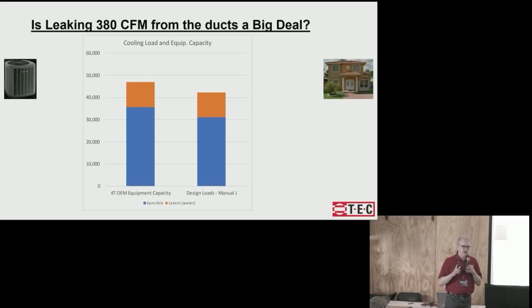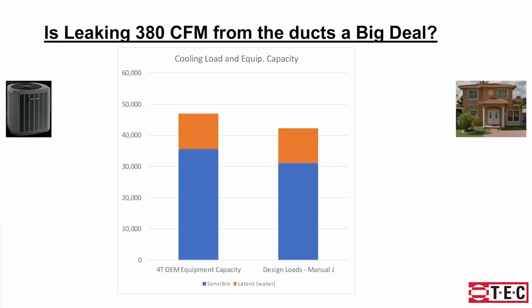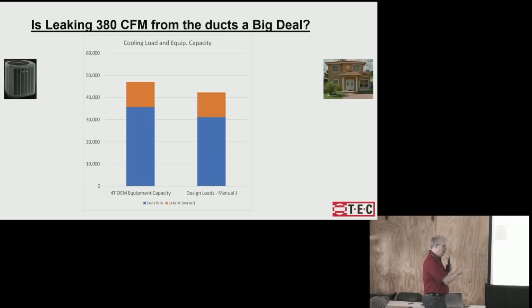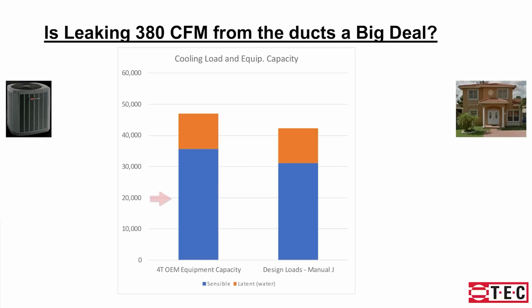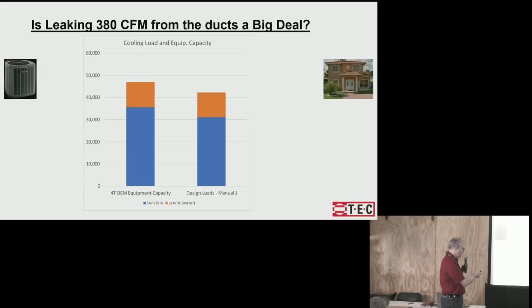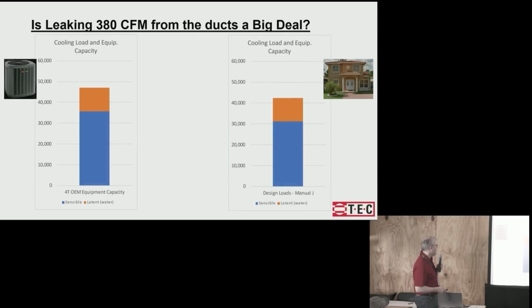So now we're going to take a closer look at that load calculation that we showed you to begin with, and we're going to correct it for what's actually happening that Manual J can't take into account. So on the left here is the equipment capacity. We're going to keep this on the left. I put the outdoor unit here to remind us that this bar is the equipment capacity, and this bar is what the house needs. So this is what the original Manual J calculation assumed, that we had this 4-ton system and that should be adequate for this house. That's where we started. But let's take a closer look now.